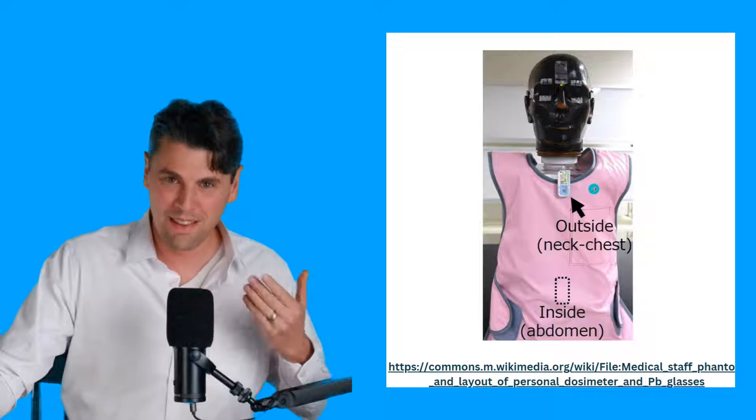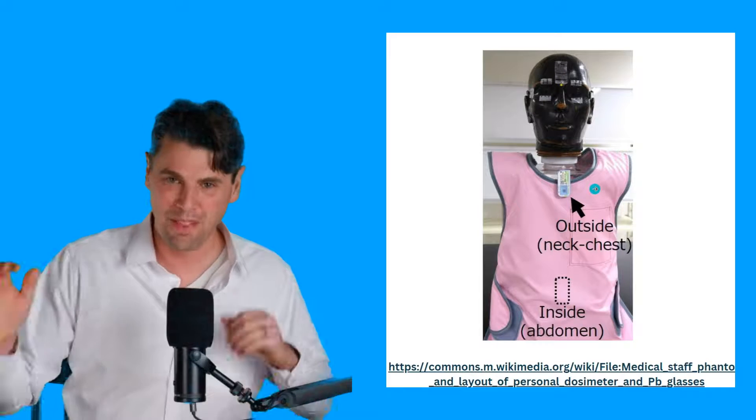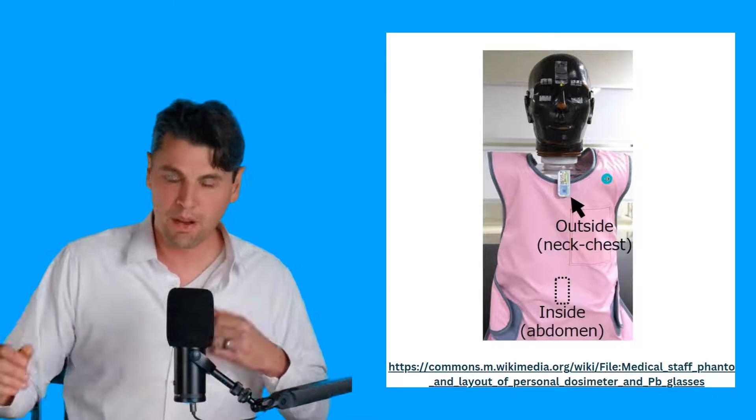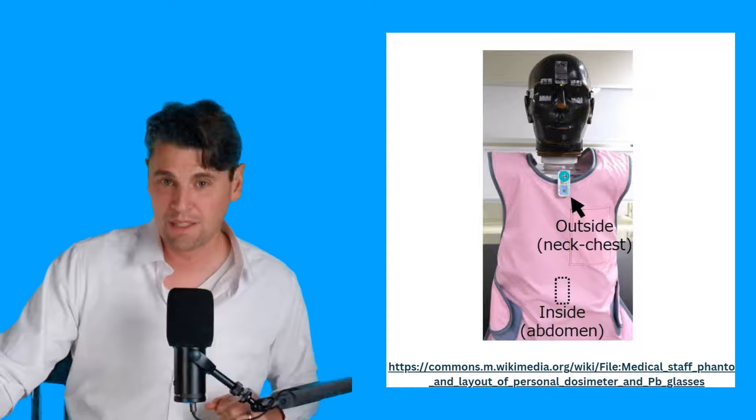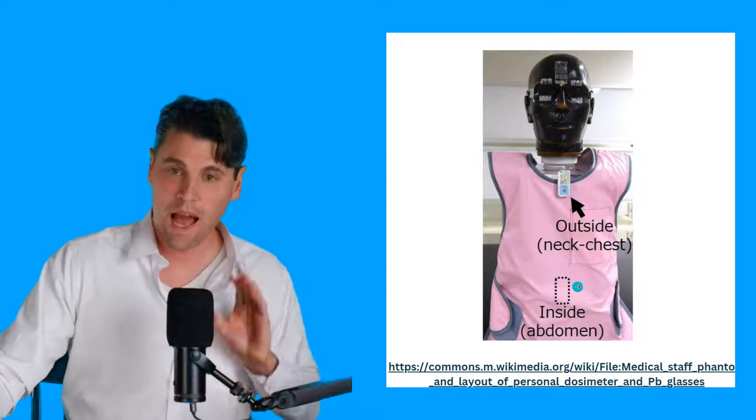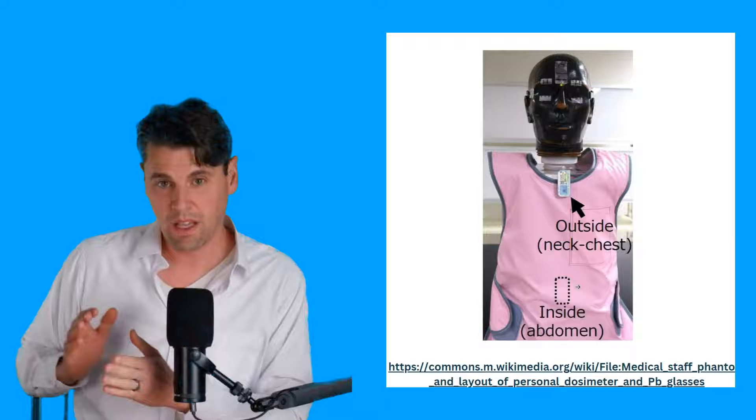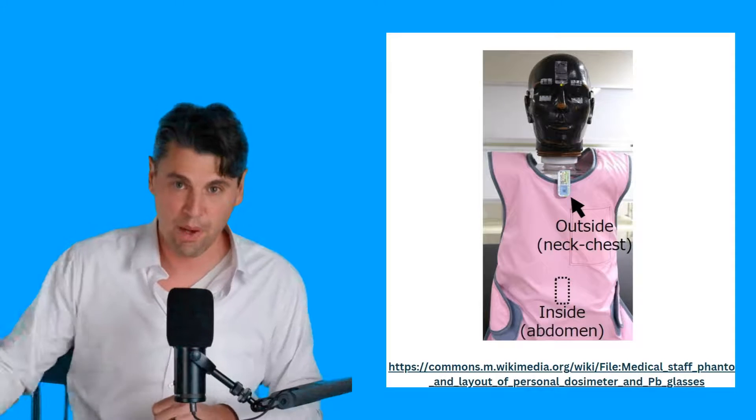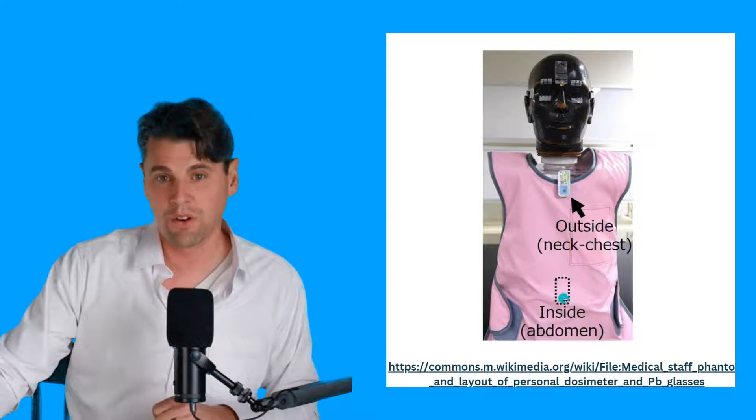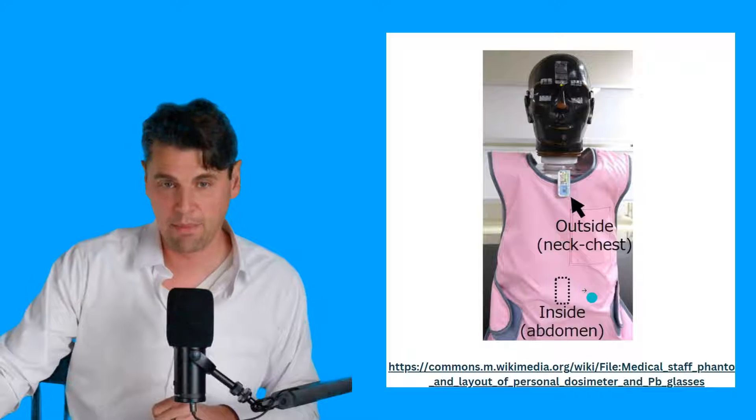A little bit less pretty, but this is an image from a paper where they were doing a study. You want to be wearing a badge at collar level outside of the lead. Optionally, you can also have a badge, especially if you're monitoring radiation exposure during pregnancy, which is underneath the lead at the abdomen level.